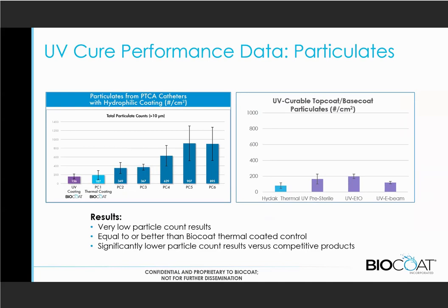So the other part of that, of course, is the particulates. And what does that look like? Again, the interesting thing is that even though the lubricity data on those various angioplasty catheters looked pretty good, the particulate data tells a slightly different story. There were, again, two different groups: one with lower particulates, and one with higher variability of the particulates. Here I'm presenting this not as total number of particles per device, but as number of particles per surface area, per centimeter squared.